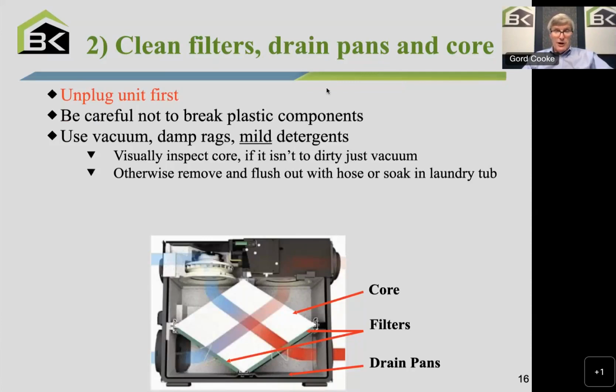More commonly or more often, it's the filters. And you'll notice the two filters there kind of on the diagonal. And as I say, 90% of HRVs look like this. Sometimes the filters are on the top of the core, sometimes on the bottom of the core, but fundamentally two filters. And you're pulling those out and you're vacuuming them. And if they're really dirty, and depending on the type, you might wash those as well. Some are washable, some aren't. These do need to be replaced, I would say, every 3 to 5 years. So check with the manufacturer, order them up. Wholesalers now have them available. Many manufacturers will just sell them online as sets. You order a set and those filters go in.